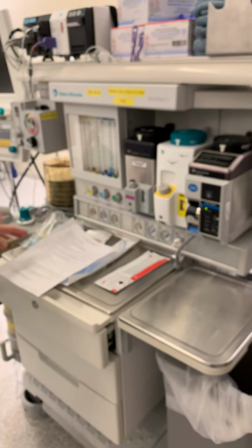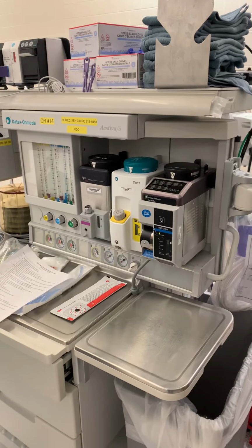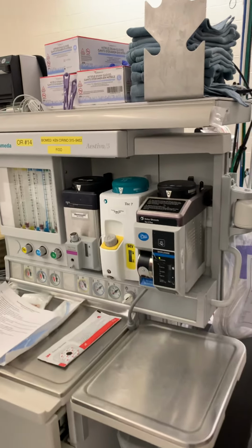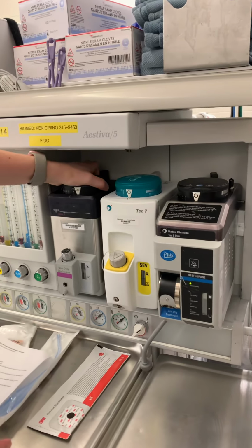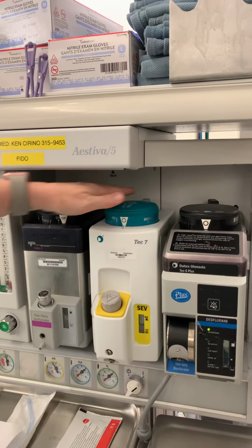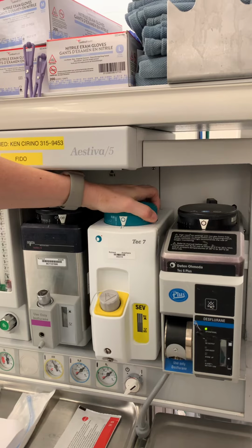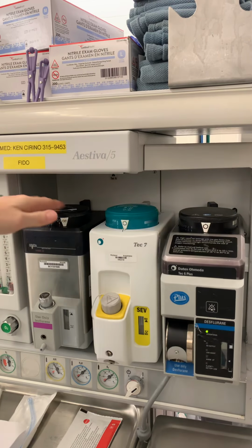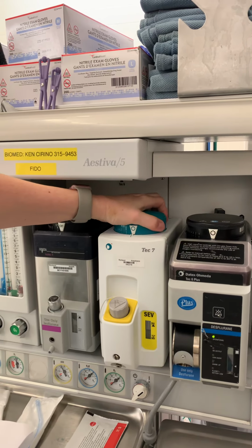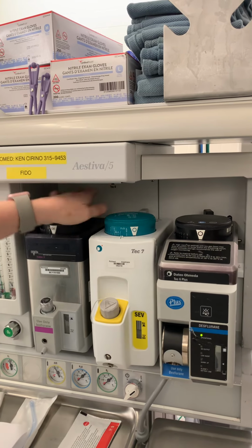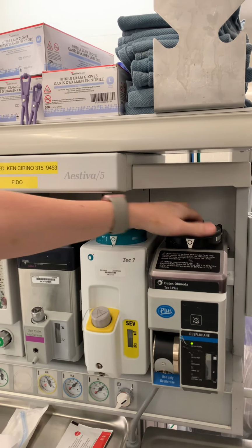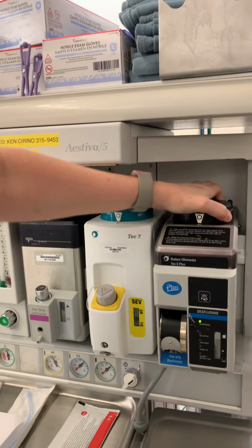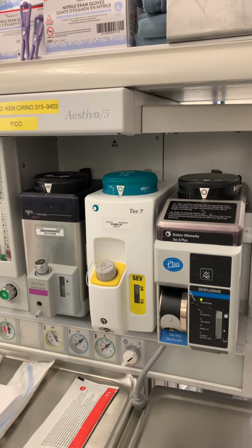So you want to make sure that you cannot turn one vaporizer on while another one is on. That's a protective mechanism. So if we turn on our ISO, we should not be able to turn on Sevo or desflurane, and that is true. And you'll run through and make sure that as one is on, you can't turn the other ones on. And desflurane just keeps sticking, so I'm just going to leave that be.